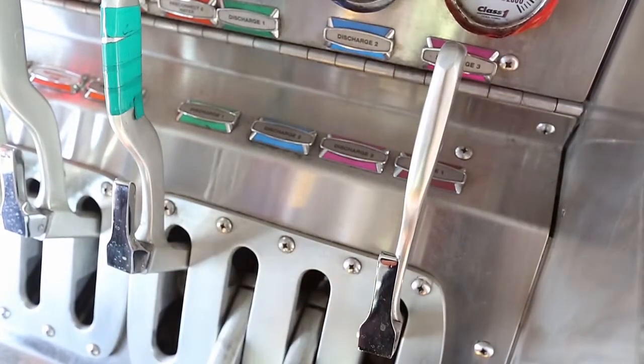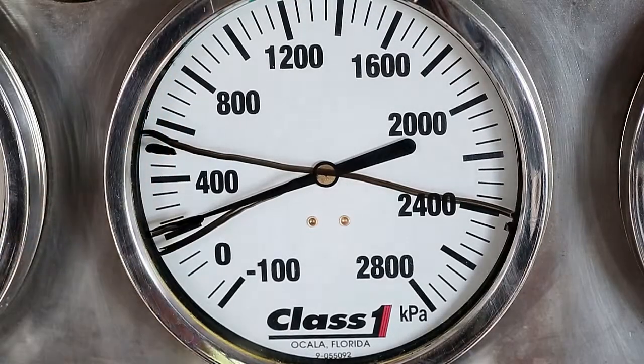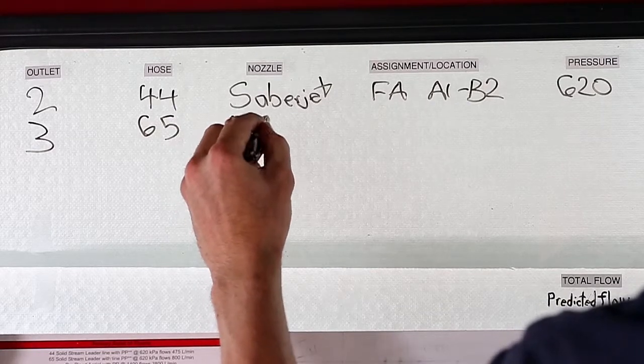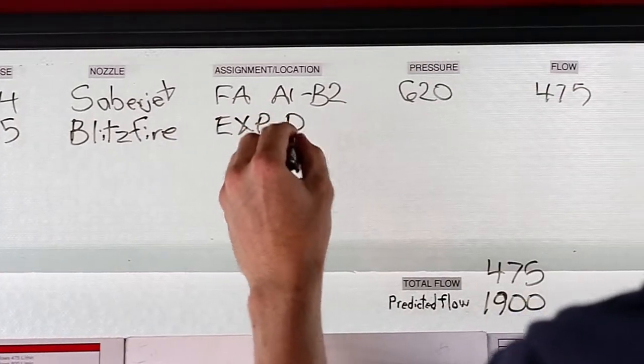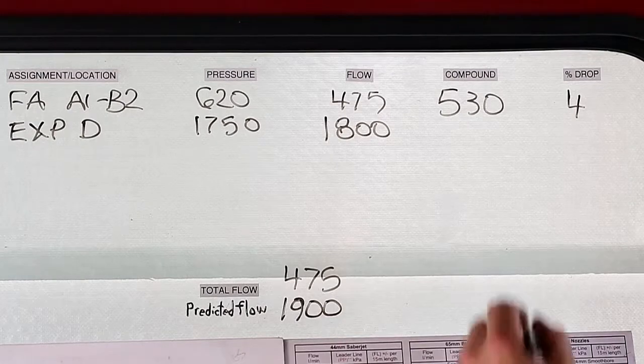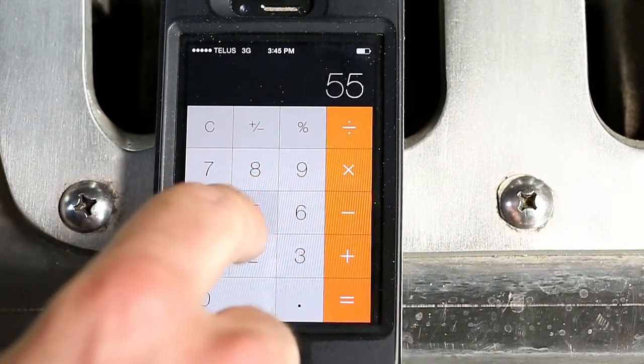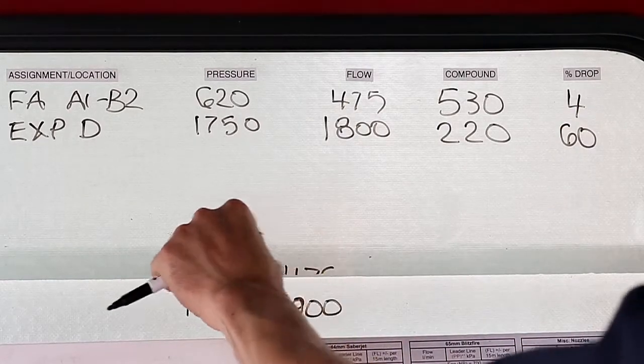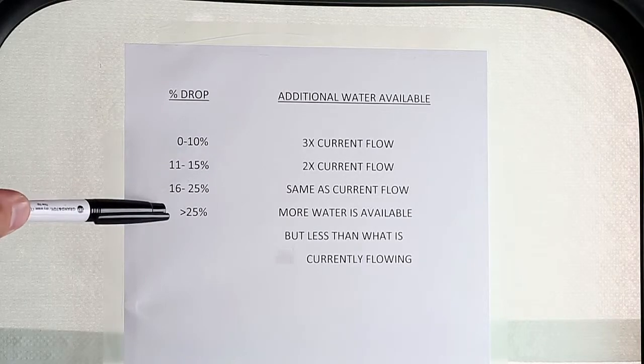Pull the next line — it's a 65 blitz fire. The compound has dropped to 220. Outlet number three, 65mm hose, blitz fire nozzle assigned to cover the exposure on the Delta side. Pressure is 1,750, flowing 1,800 litres a minute. The compound is now at 220 kPa. The drop is 310 divided by 530, which gives us 60%. Adding 475 and 1,800, our total flow is 2,275. Checking the chart, we're above 25%.